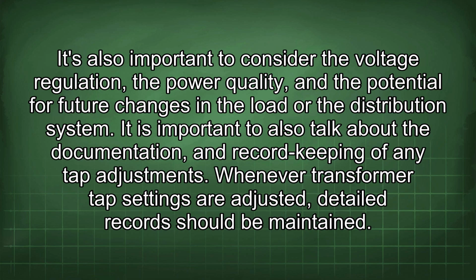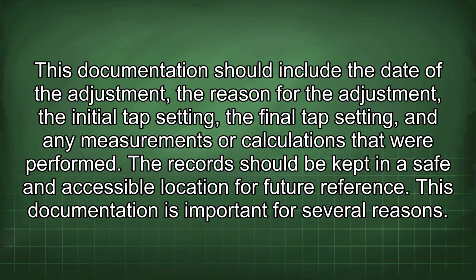Whenever transformer tap settings are adjusted, detailed records should be maintained. This documentation should include the date of the adjustment, the reason for the adjustment, the initial tap setting, the final tap setting, and any measurements or calculations that were performed. The record should be kept in a safe and accessible location for future reference.